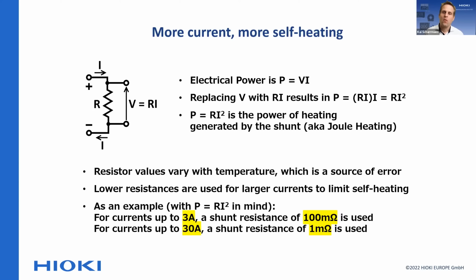Now, what you have to do if you use high currents in a shunt is massively lower the resistance of the shunt. Because you have this square in the formula, if you want to produce the same amount of heat with 30 amps compared to 3 amps, then you basically have to reduce the shunt size from 100 milliohms to, say, 1 milliohm. So by a factor of 100, you have to lower the resistance value if you increase the current that you want to drive through it by a factor of 10. That means that the shunt values are then very, very low.